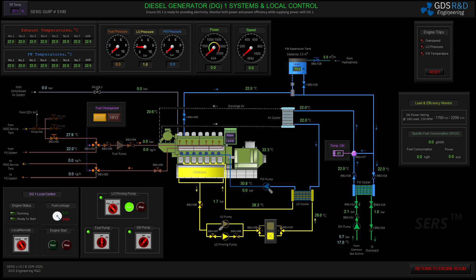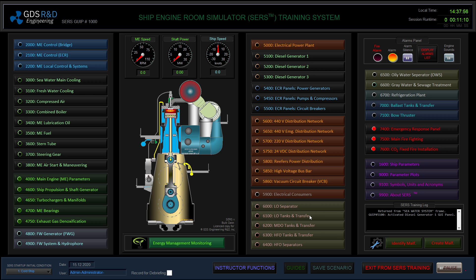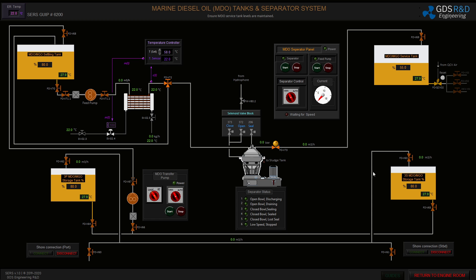Now lubricating oil: I will start the lubricating oil priming pump in manual mode. There is about two bar of oil pressure at the engine inlet. Now I will line up the diesel oil line for my diesel generator.